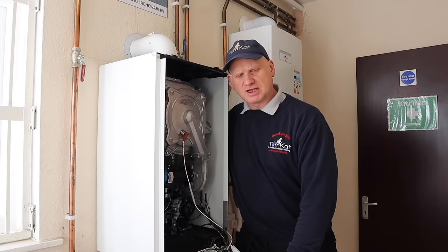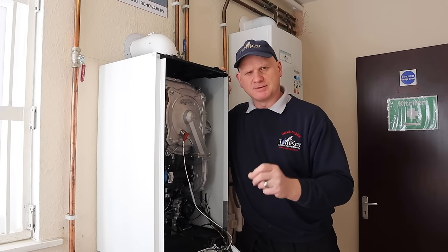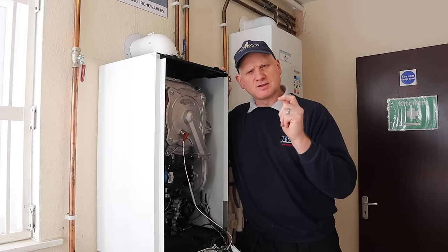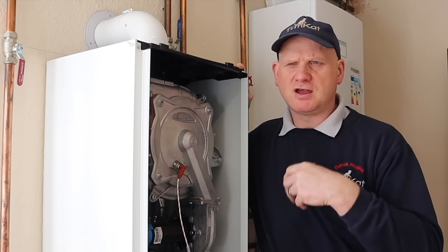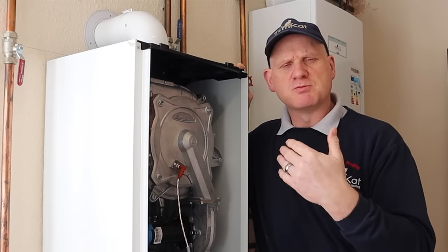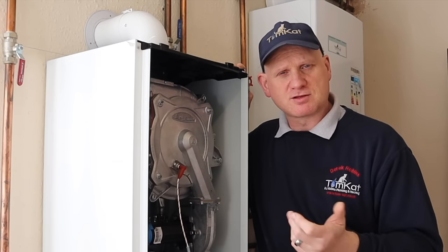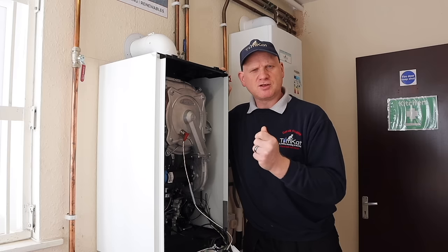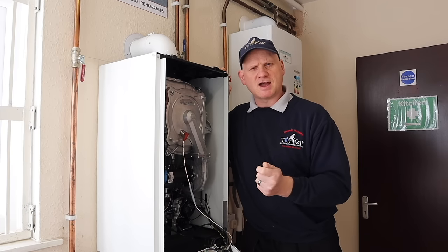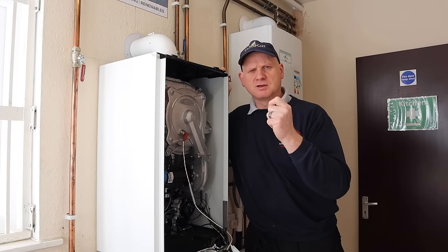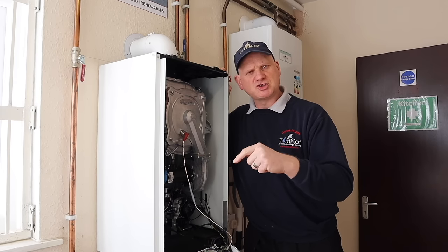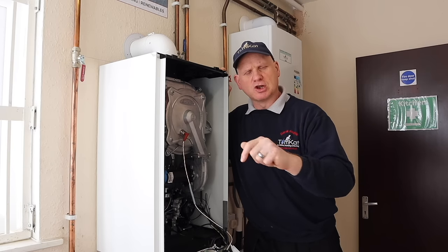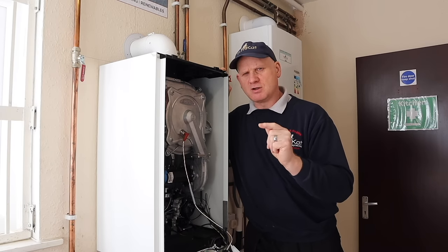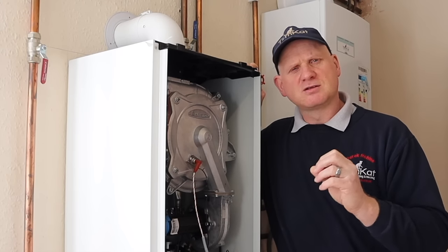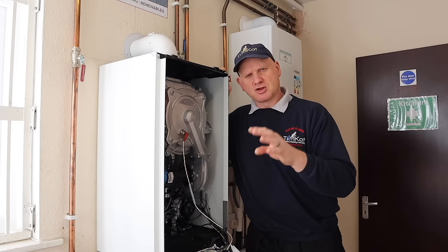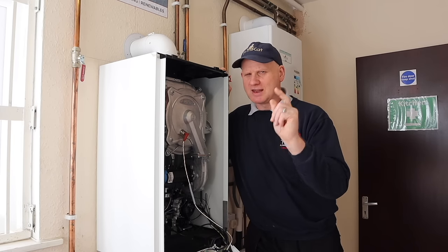Now, we've been going on about modulation. All modern boilers, like I say, modulate, but they don't all modulate down to the same kilowatt. So you could have, say, a 24 kilowatt boiler which modulates down to 4 kilowatts on the lowest setting, or you could have a 30 kilowatt one that modulates down to 2.5 kilowatts. So in a small house, the bigger boiler would be more efficient because you would be able to modulate it down to a lower rate. That sounds a bit weird, but that's how it works. Where combis are concerned, the high kilowatts for the water is good, but if it's got a low modulation as well, that's even better.